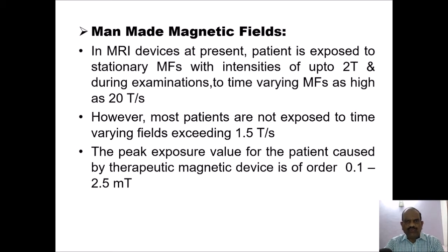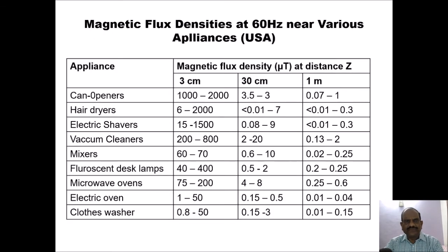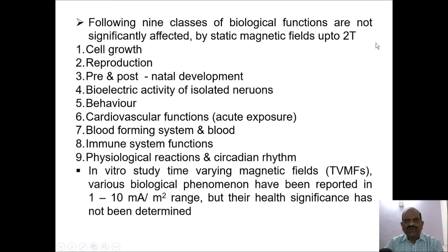The peak exposure value for patients caused by therapeutic magnetic devices is of the order of 0.1 to 2.5 milliTesla. The following nine classes of biological functions are not significantly affected by static magnetic fields: cell growth, reproduction, pre- and post-natal development, bioelectric activity of isolated neurons, behavior, cardiovascular function even during acute exposure, blood-forming system and blood, immune system functions and physiological reactions, and circadian rhythm. These nine classes are not significantly affected by static magnetic fields up to 2 Tesla.